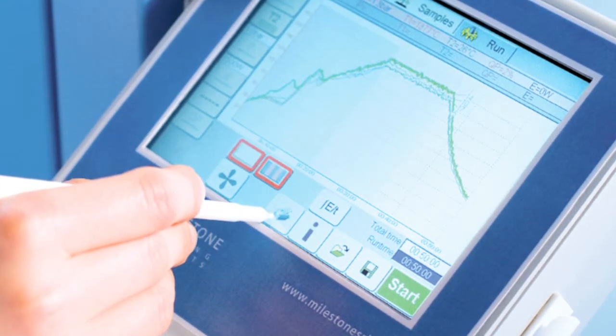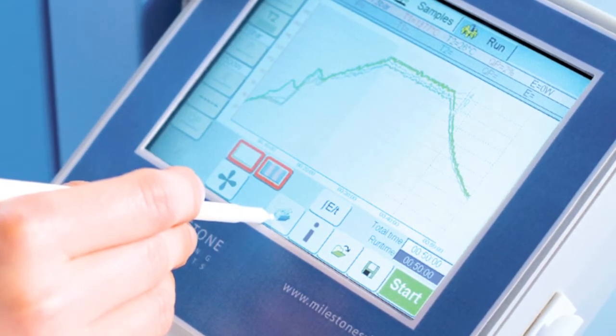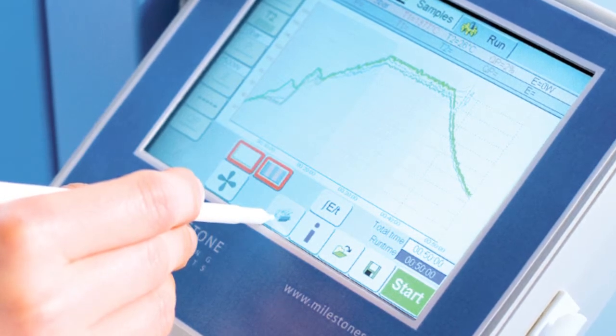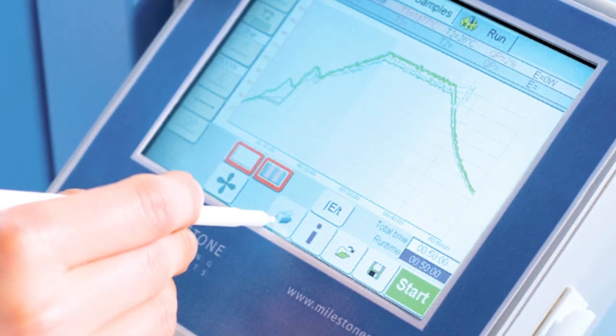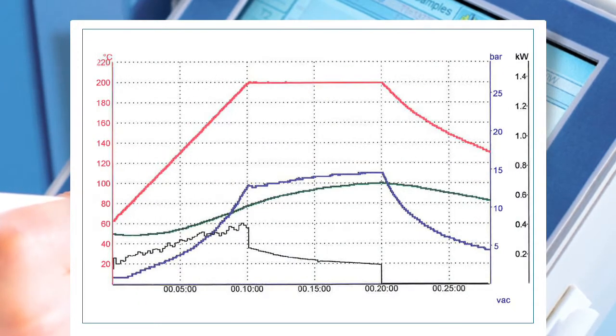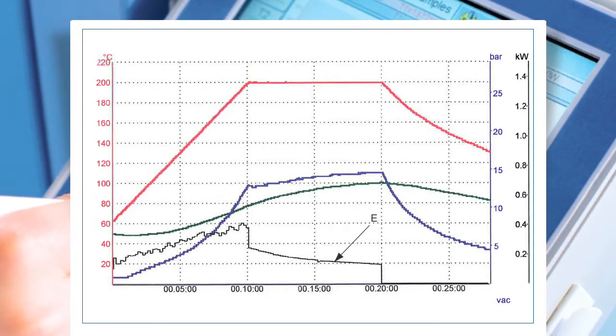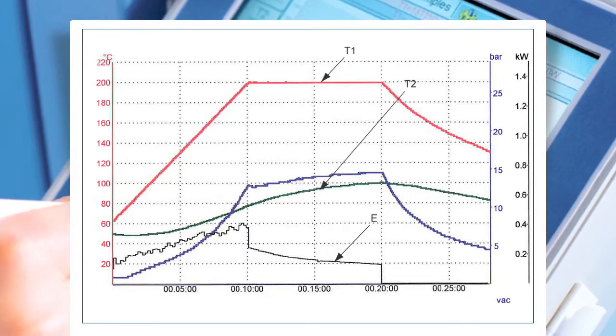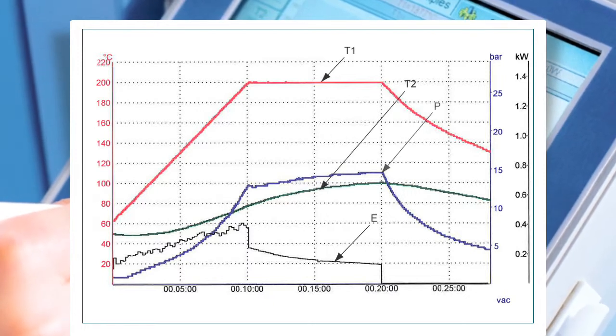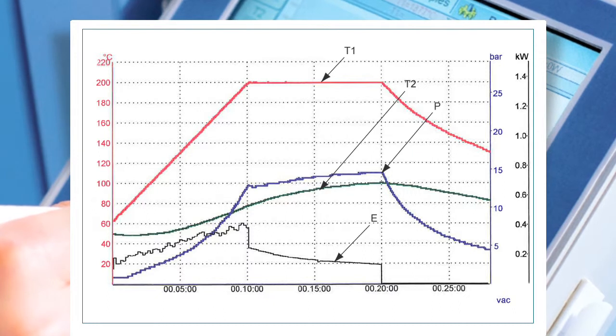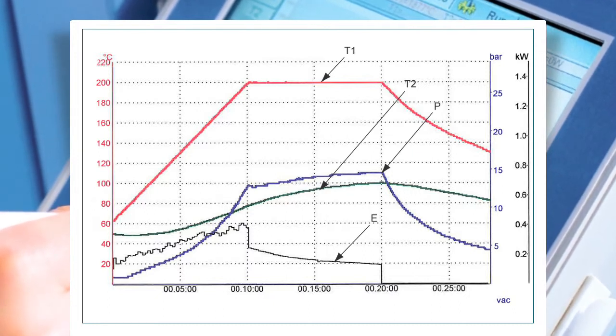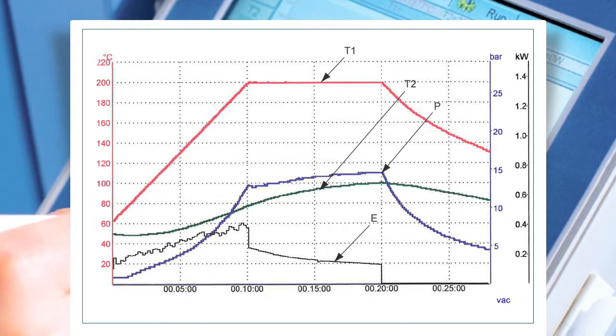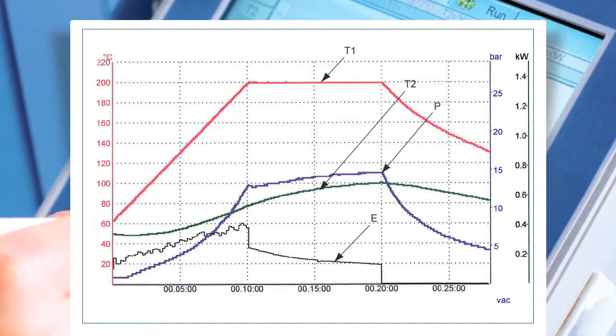Another great feature of EasyControl is that there is no need to select different power levels as the EasyControl's PID controller monitors and records temperature 20 times per second. The system will automatically adjust microwave power output to follow the desired temperature program regardless of rotor or number of vessels being used. This feature also enables the system to react instantaneously to exothermic reactions and immediately suspend microwave emission.